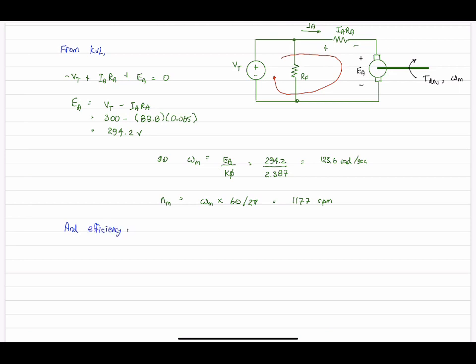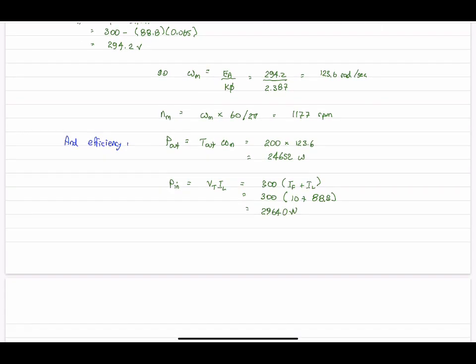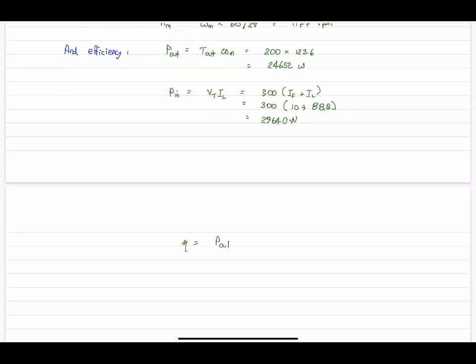So let's round it out now with efficiency. We have to calculate the power out. This is the power delivered to the load. And so that was 200 newton meters times the speed that we just calculated, so 24,652 watts. On the electrical side, the total power in delivered by that source is the voltage 300 times the total current, which is the sum of the armature and the field current. And so the efficiency then is just the ratio of the two of these times 100 percent. So this comes out to 83.2 percent efficiency.